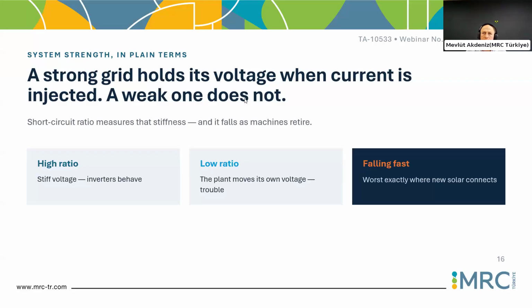But this provides short circuit strength. This provides the protection scheme with high enough capability to protect the grid or to intervene. But this does not by itself provide reactive power capability in terms of reserve. If our machines, the power plant synchronous generators, are operating at their higher limit at the same short circuit value, in case of any motor start, FIDVR, a fault induced delayed voltage recovery case, or if we need some reactive power jump at the grid level, these machines cannot provide this overshoot or high reactive power during those transients, because even with a high short circuit level, their capacity or capabilities are already utilized.